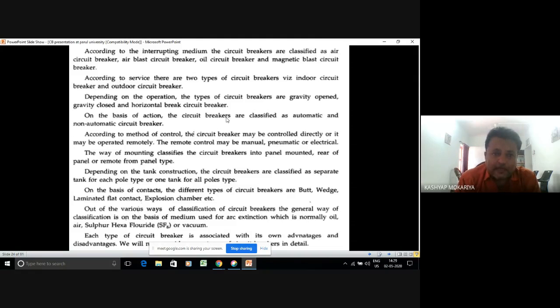On the basis of the action, circuit breakers are classified as automatic and non-automatic circuit breakers. According to the method of control, a circuit breaker may be operated directly or remotely. This is a very important feature. In most of the bigger industries now, all the breakers are operated from the control room, so you do not even require to go to the site. But yes, the operation department person has to go on site because he has to discharge the cable by the rod. So that's why you have to go to the site.